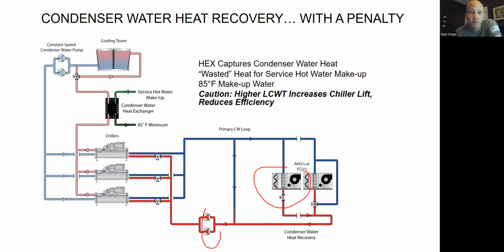Instead of 2. But what I'm going to do is recognize the fact that, hey, I'm going to run this chiller plant in the middle of winter. I don't need all 3 machines, but I need 1 machine in the winter, right? Because I don't have a lot of cooling to do. I only got to cool the interior. I don't have to cool the exterior. That's heating season for those people. So I got to cool the interior.